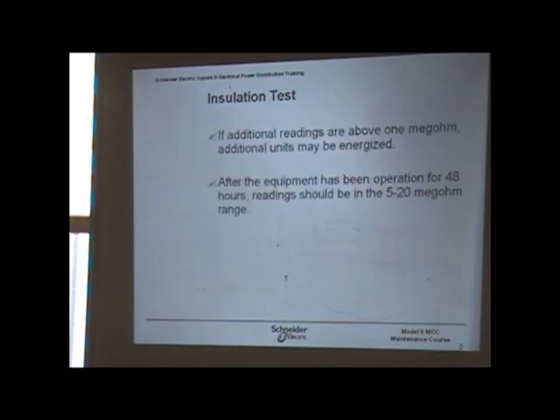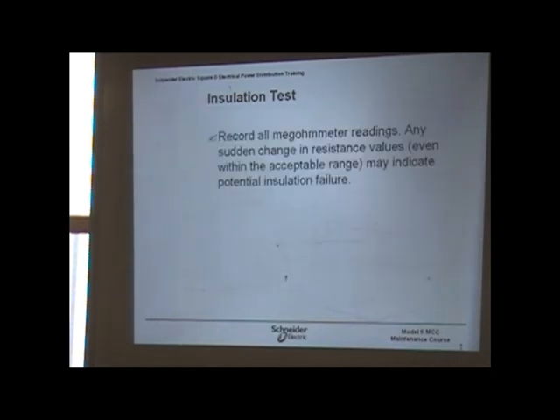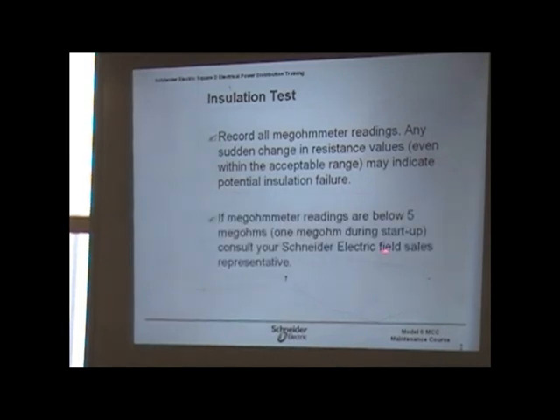Okay. Once again, this one says that readings should be between 5 to 20 megohm range if it's been in operation for 48 hours, but more than anything else, it's always 1 megohm during startup, 5 megs after, if you had it running before and now you're going back and re-energizing.